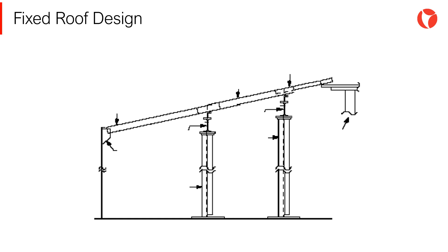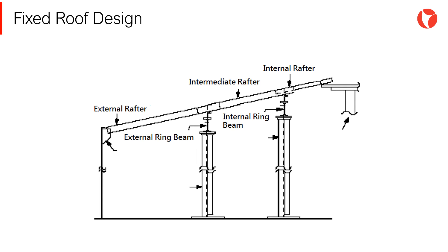Let's take a closer look at these three elements in a large diameter tank. In this case, there are three rows of rafters: external, intermediate, and internal. These rafters will be supported by two ring beams, one external and one internal. In turn, two rows of columns and the central column are needed to support the ring beams.